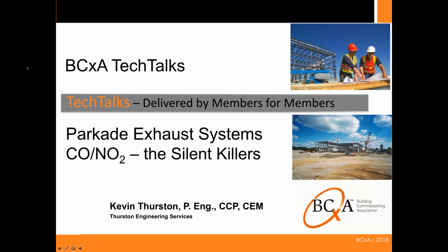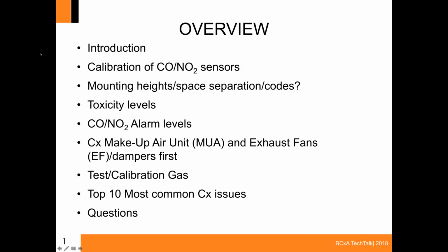Thank you very much, Sherry, and thank you to everybody who's attending today. In my presentation today, talking about Parkade exhaust systems, first of all, in Canada, we call them Parkades, and basically it applies to any type of covered parking garage, whether it be underground or above ground. In my talk today, I'm going to talk about the calibration of the sensors, the mounting heights, the space separation that they should have in terms of the square footage in the parking garages, the toxicity levels of CO and NO2, the alarm levels that you would be looking for, the commissioning of the makeup air system, the MUA, and the exhaust fans, and the dampers.